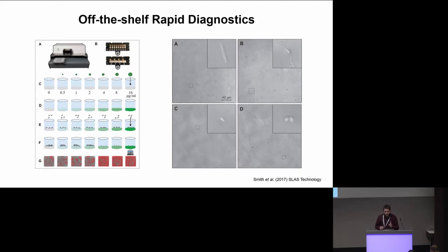So really what we've done is we've developed not only a microdilution series, but also we've inoculated that simply by doing 2 pipetting steps, which this process takes many, many steps to do manually and is well outside the technical capacity of most clinical laboratories. After we inoculate the cells, we can then incubate them, and in this case we incubate them for 2 hours, and monitor by automated microscopy.